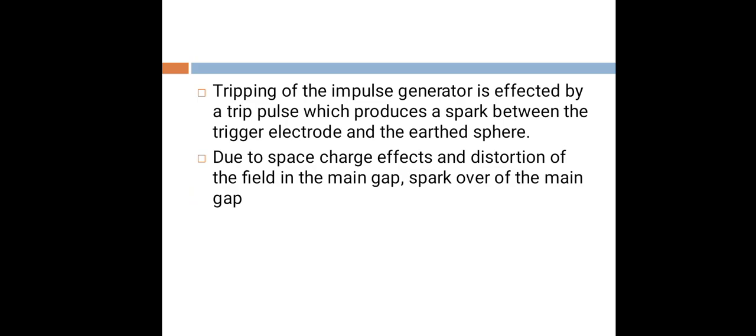Tripping of the impulse generator is effected by a trip pulse which produces a spark between the trigger electrode and the earthed sphere. Due to space charge effects and distortion of the field in the main gap, sparkover of the main gap occurs. Thank you.